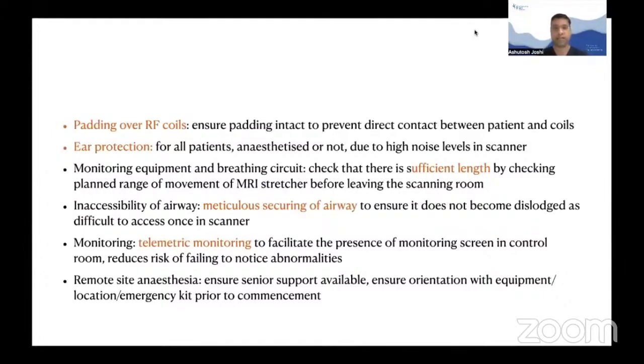The monitoring equipment and the breathing circuits should have sufficient length, checking the planned range of movement of the MRI stretcher before leaving the scanning room, and we should always meticulously secure the airway to ensure that it does not become dislodged. Telemetric monitoring is desirable as it reduces the risk of failing to notice abnormalities.